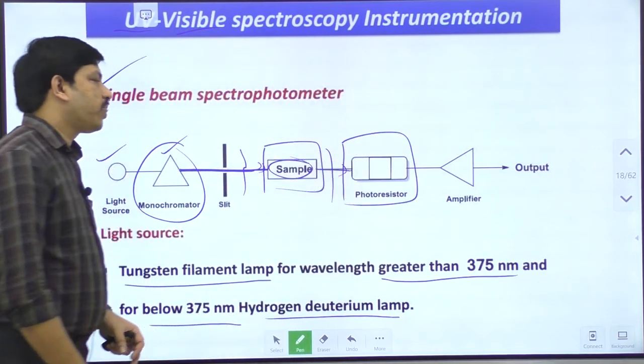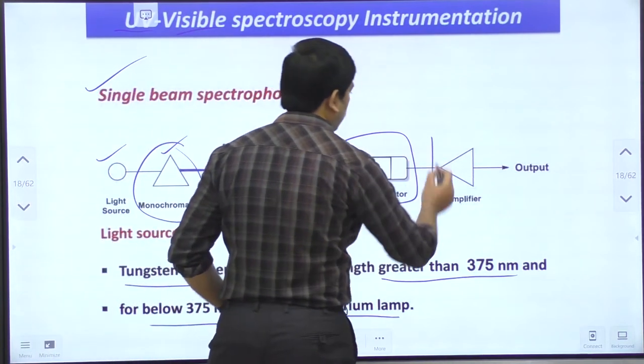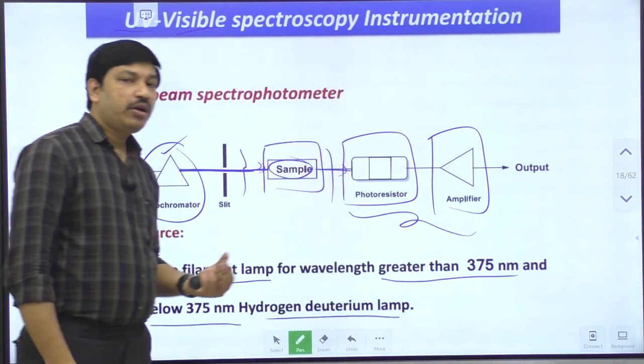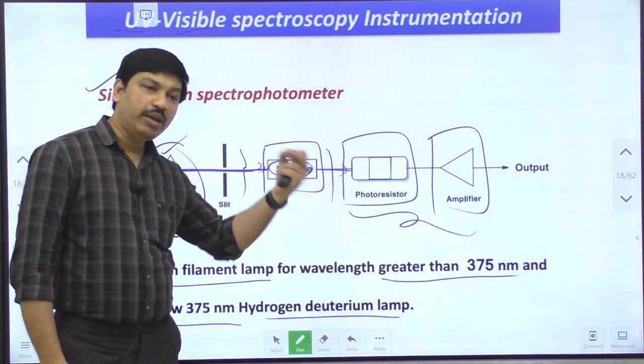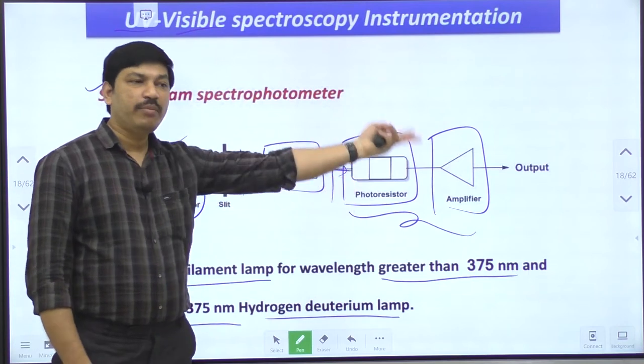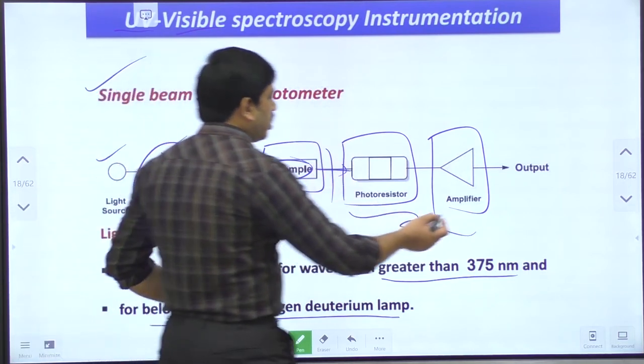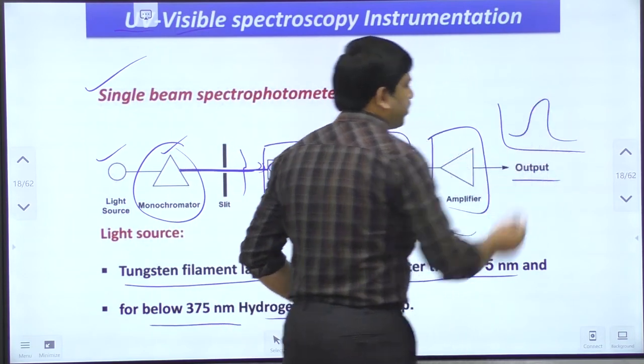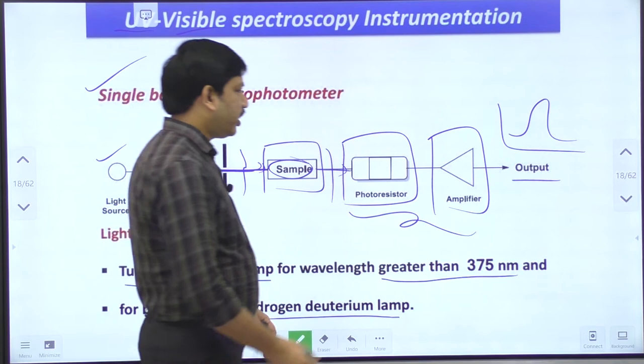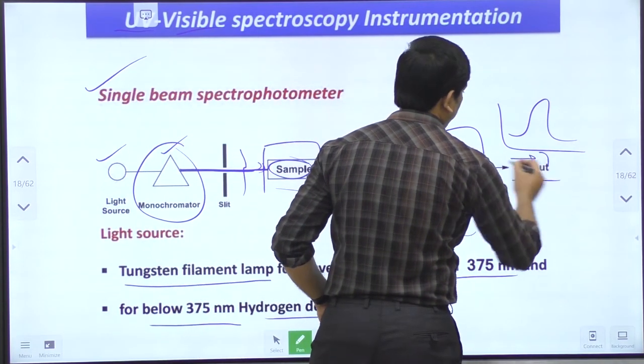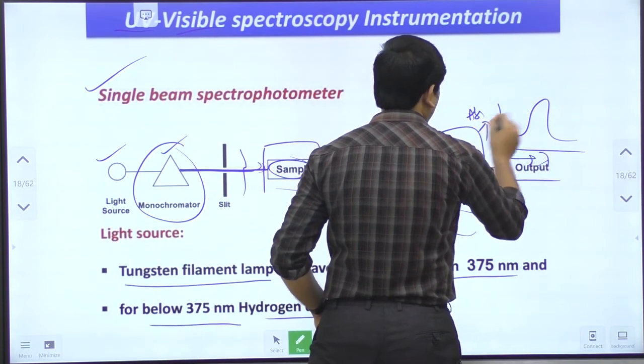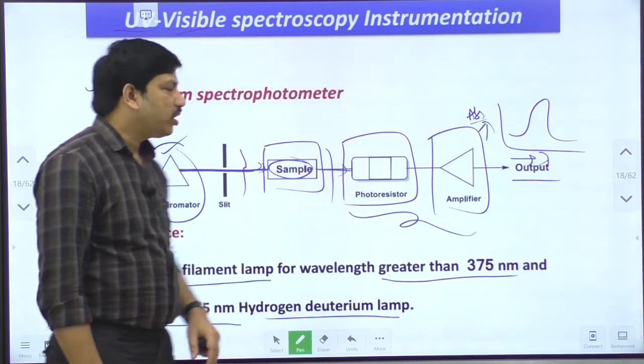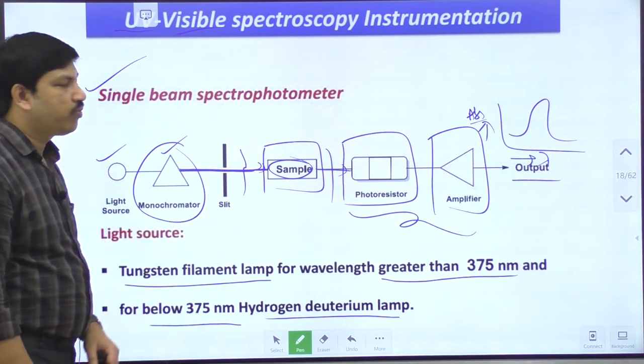The transmitted radiation goes to a photodetector, followed by an amplifier. These two components detect how much radiation was absorbed by the sample and how much came out. The result is displayed as an absorption spectrum, with wavelength on the x-axis and absorbance values on the y-axis. This is how the single beam spectrophotometer works.